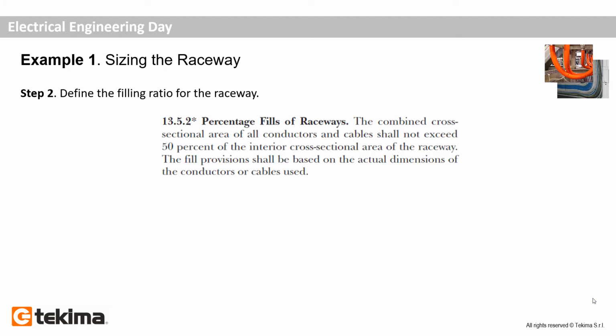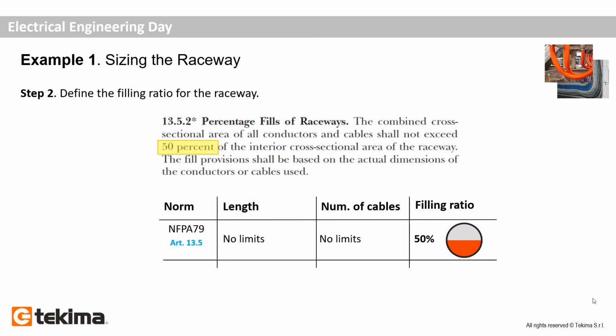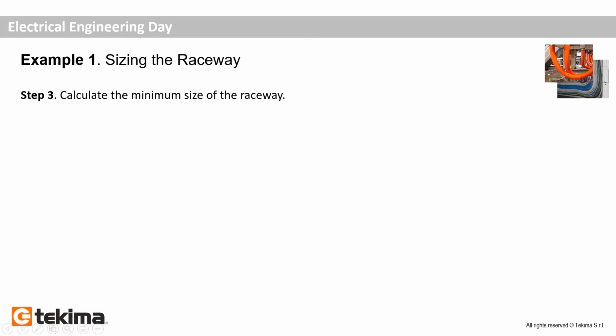What is the percentage of cross-sectional area of the raceway that we can use for the cabling? According to NFPA 79, we can reach up to 50% of the interior cross-sectional area. We don't have any limits in the length and any limits in the number of cables contained. Step 3. Calculate the minimum size of the raceway.